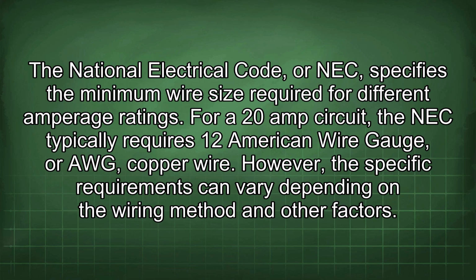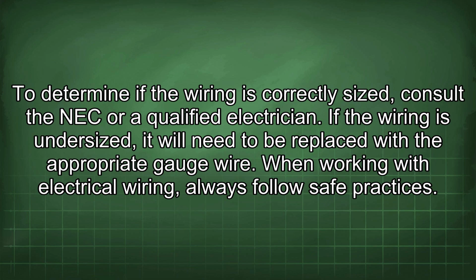The National Electrical Code, or NEC, specifies the minimum wire size required for different amperage ratings. For a 20 amp circuit, the NEC typically requires 12 American wire gauge, or AWG, copper wire. However, the specific requirements can vary depending on the wiring method and other factors. To determine if the wiring is correctly sized, consult the NEC or a qualified electrician. If the wiring is undersized, it will need to be replaced with the appropriate gauge wire.